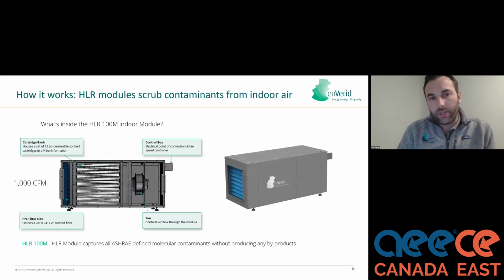Drilling down just on one of our units here, it's just that simple. We have a pre-filter here in front of our sorbent filter bank. You change that pre-filter on your regular MERV filter replacement cycle. But these sorbent filters are good for 2 years. And then we have our own internal fan so that this system can be easily retrofitted or deployed in new construction without increasing static across the systems.